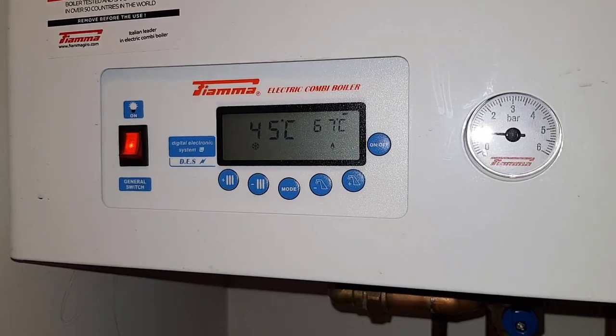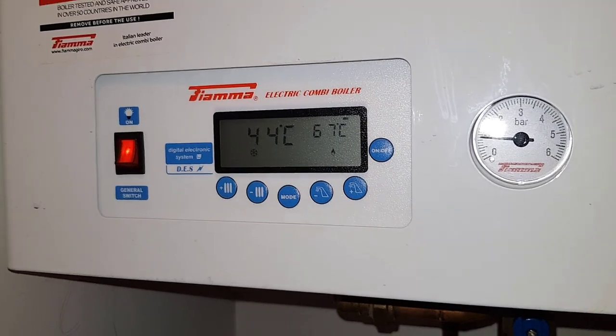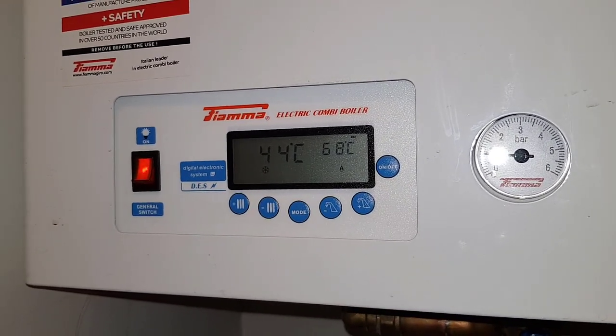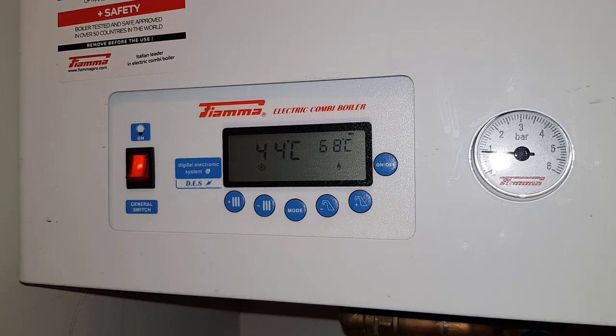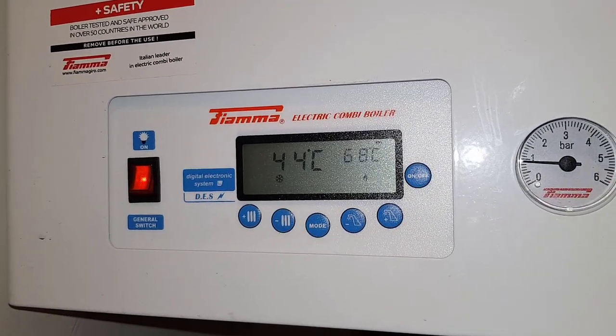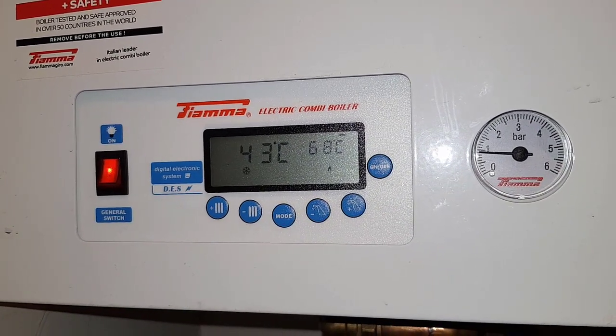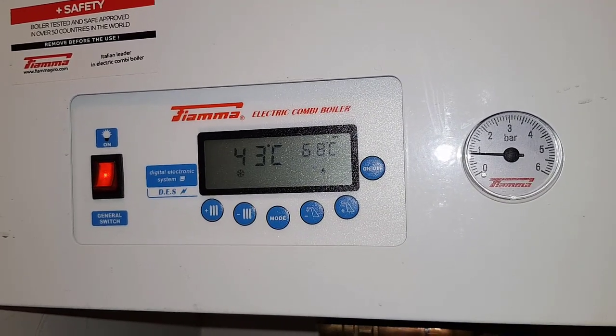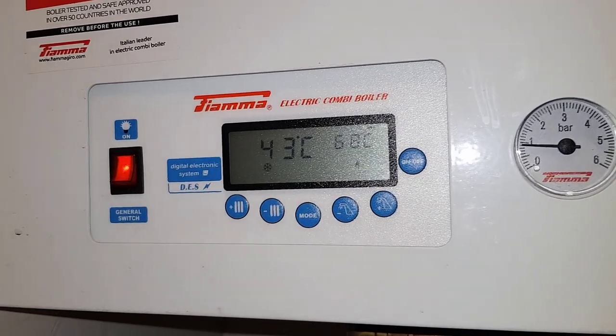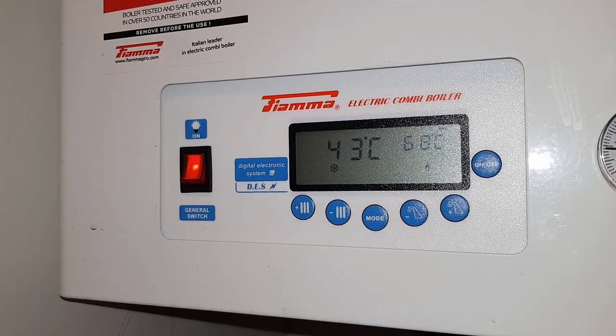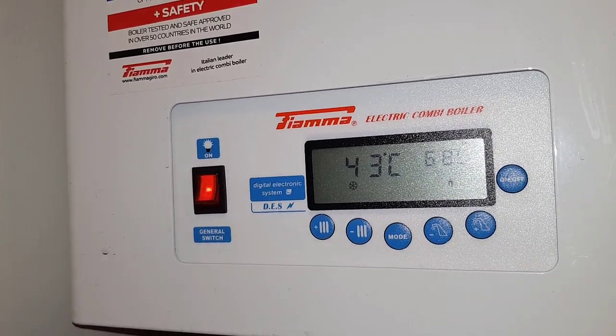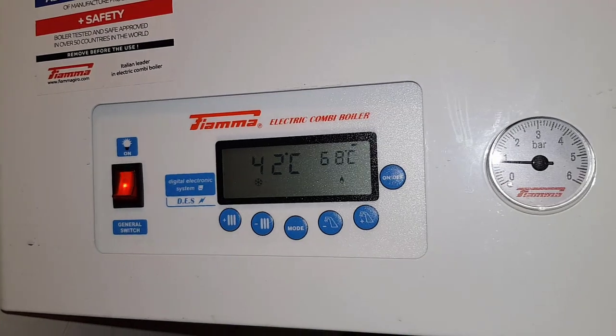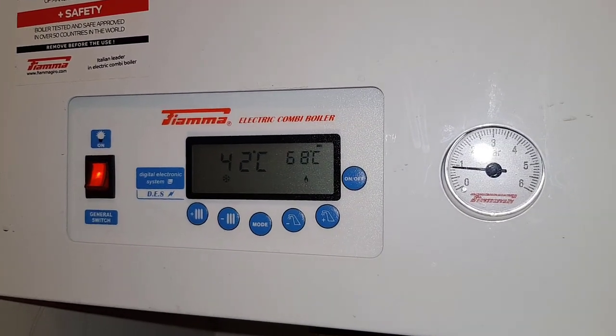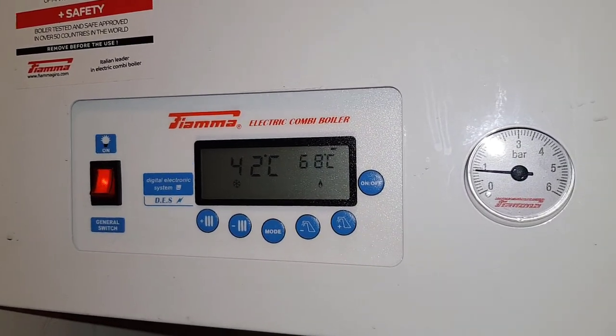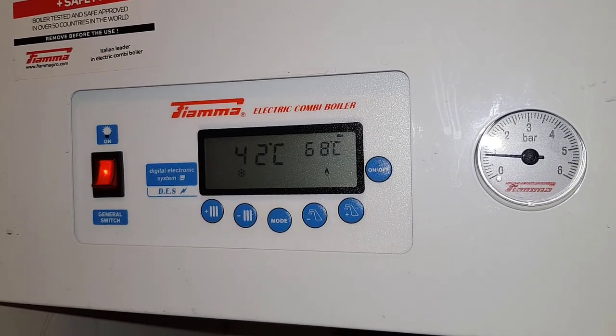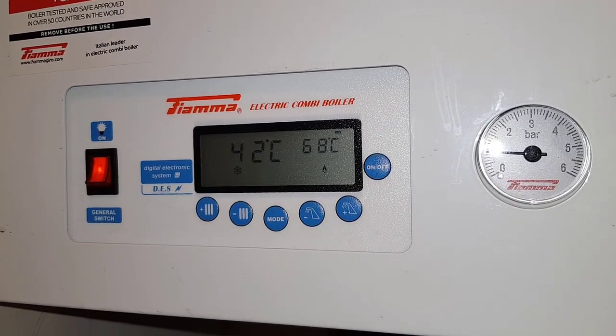It might be a bit difficult to understand this, because it's quite a tricky fault, and it was tricky for me to figure out what was going on. So it's quiet like this. The pump should come on either if there's a heating demand, the heating's on and tells it to come on, or for the hot water to be heated once the tap's running. We'll run the tap again and go through this again so you can see clearly what's going on.